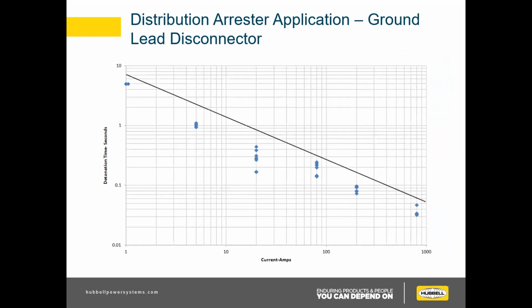So here is the ground lead disconnector curve that I was talking about. The IEEE standard requires that it operate at a minimum of 20 amps. In our case, we can operate down to 1 amp if we see that 1 amp of current for about 8 or 9 seconds. So we have to see the current for that long. But anyway, that pretty much guarantees that your breaker's not going to operate and lock out your system. And if you have a super high current, over 100 amps, it's going to take less than a tenth of a second for the disconnector to operate.